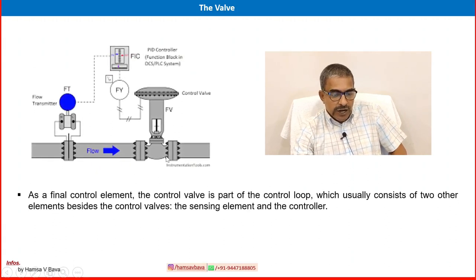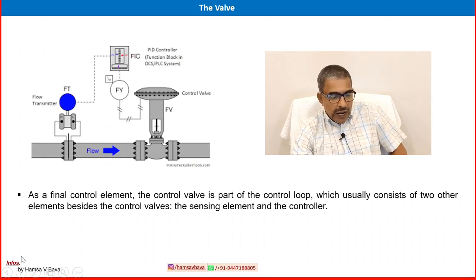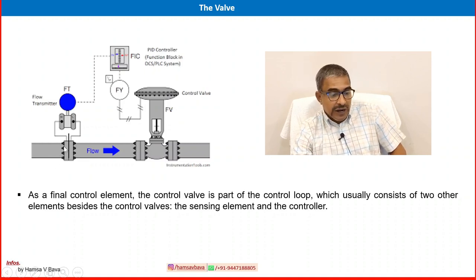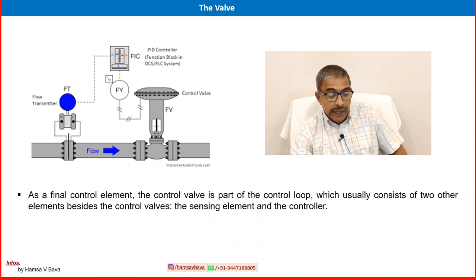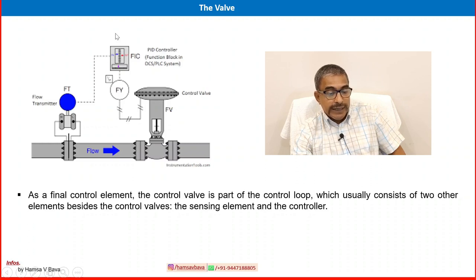One more explanation on the control system: the control valve as a final control element is part of the control loop, which usually consists of two other basic elements — the sensing element and the controller. The sensing element is located in the process and measures flow, pressure, temperature, or level. It converts the measurement into a signal provided to a transmitter — in this example, a flow transmitter. The transmitter converts the signal into a suitable communication method, either pneumatic or electronic, and sends it to the controller, which is hardware located in the control room or local equipment room, called the FIC — flow indicator controller.